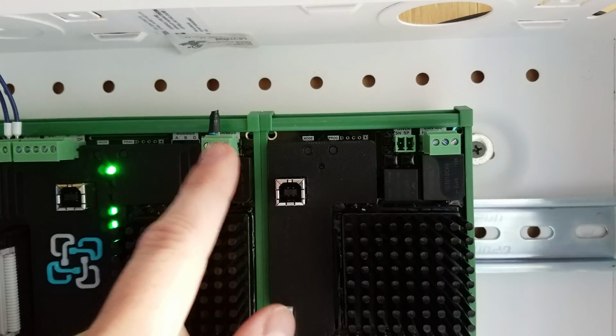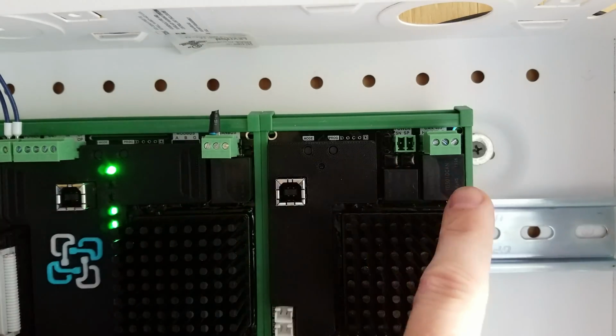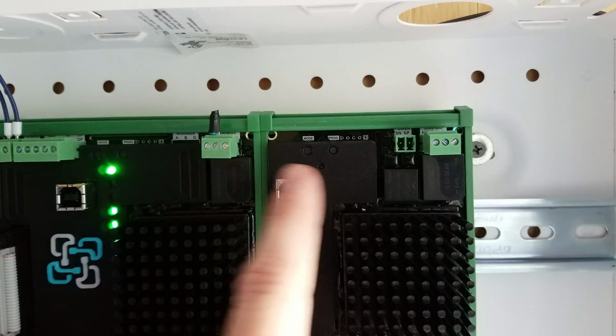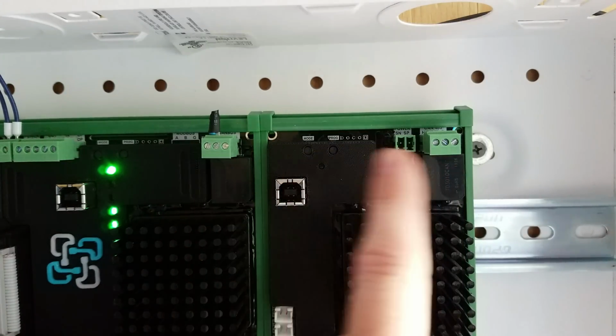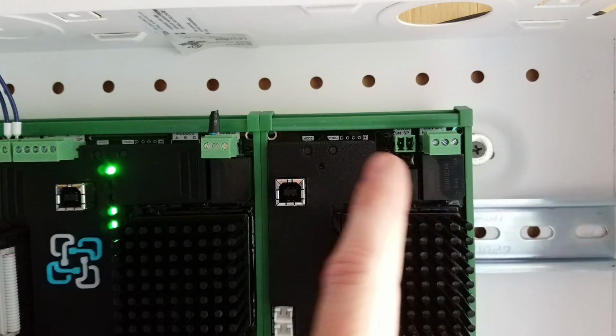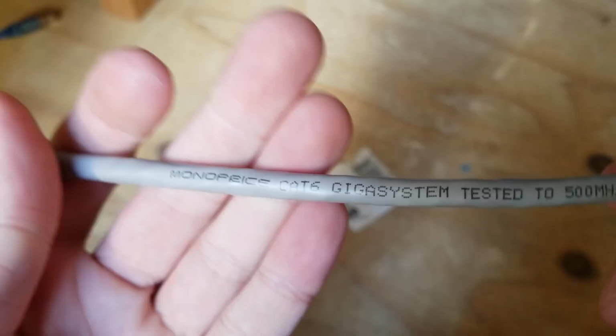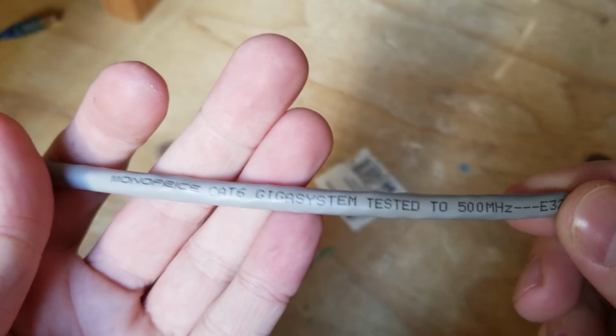I did ask Batrium about the ground, and they said the ground pin only needs to be connected if you're doing a long run of wire, or if you need to isolate from interference. Since this is only a couple of inches here, I'm not going to bother with it. So to make the wire for the CAN bus connection, I just took a small piece of category 6 Ethernet cable.